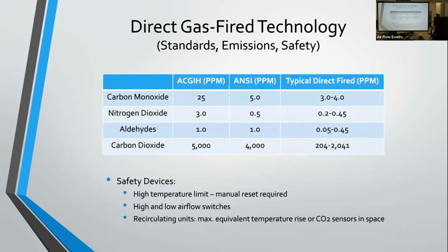We mentioned these are very low emissions burners, but let's put some numbers to it. The industrial hygienists limit your maximum threshold value of carbon monoxide to 25 parts per million. Those ANSI standards I just mentioned limit the carbon monoxide rise through a direct fired unit to 5 parts per million, significantly less than the industrial hygienist limits. But you'll actually see about 3 to 4 parts per million on a direct fired burner. So this is in the discharge, or in the space? This is the rise through the unit. Okay, so discharge essentially. Yes. So your actual field levels are a lot lower than that. Yeah, exactly.